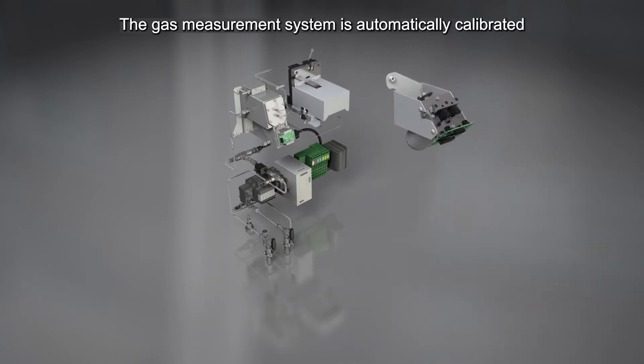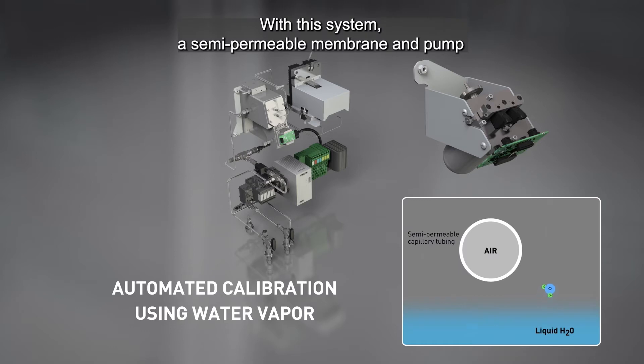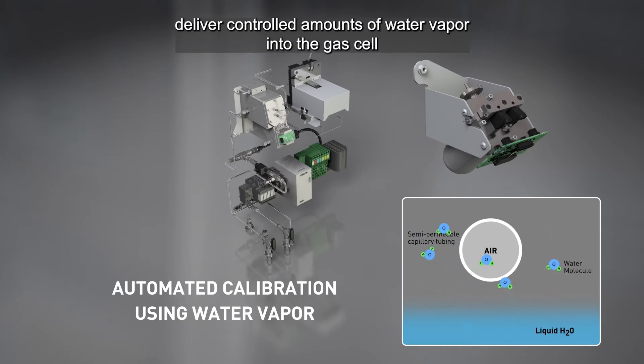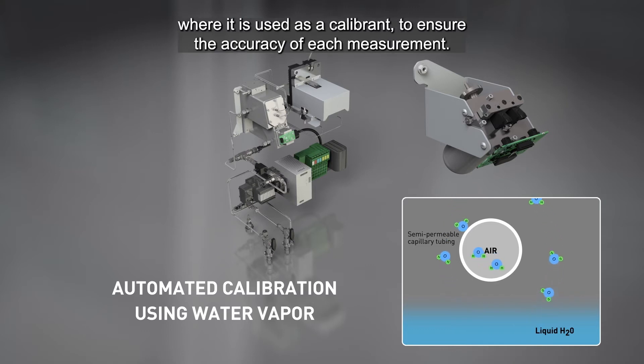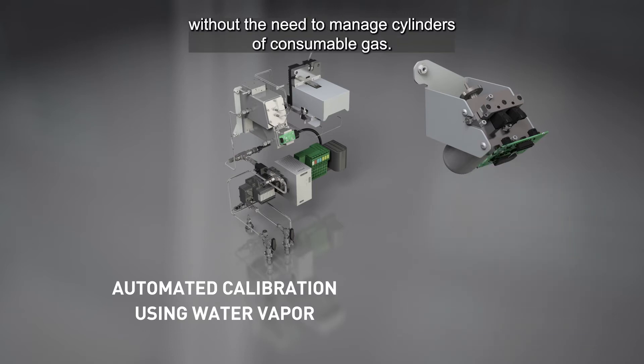The gas measurement system is automatically calibrated using a patented onboard calibration system. With this system, a semi-permeable membrane and pump deliver controlled amounts of water vapor into the gas cell, where it is used as a calibrant to ensure the accuracy of each measurement. The Callisto R9 auto calibration method ensures long-term DGA accuracy without the need to manage cylinders of consumable gas.